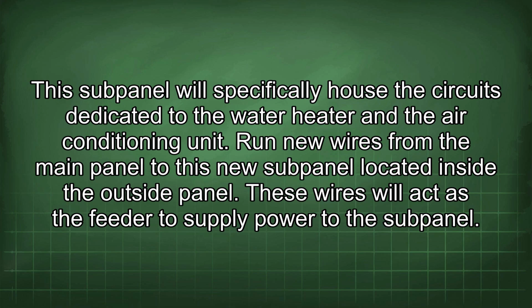This subpanel will specifically house the circuits dedicated to the water heater and the air conditioning unit. Run new wires from the main panel to this new subpanel located inside the outside panel. These wires will act as the feeder to supply power to the subpanel.